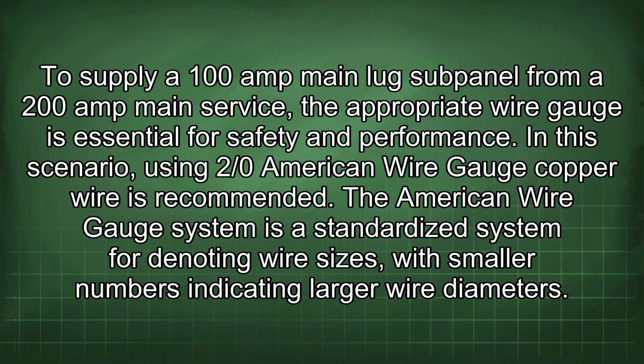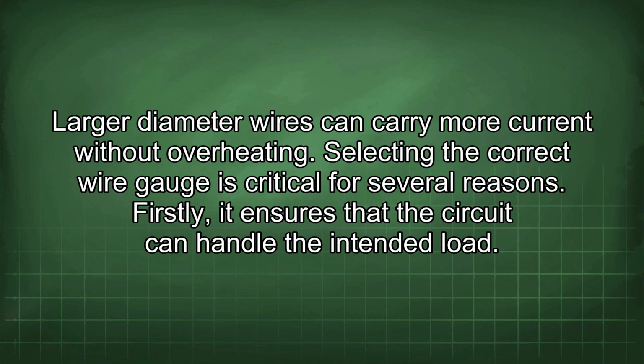To supply a 100 amp main lug subpanel from a 200 amp main service, the appropriate wire gauge is essential for safety and performance. In this scenario, using 2/0 American wire gauge copper wire is recommended. The American wire gauge system is a standardized system for denoting wire sizes, with smaller numbers indicating larger wire diameters. Larger diameter wires can carry more current without overheating.